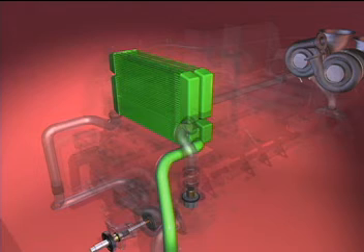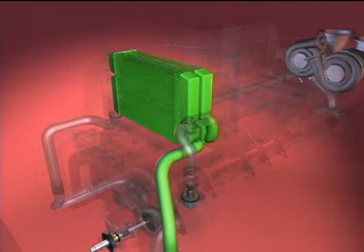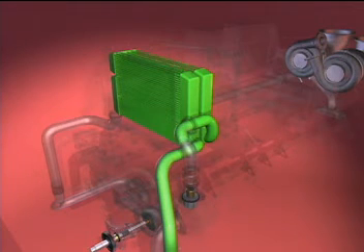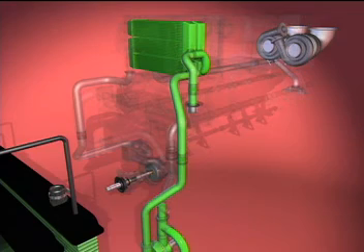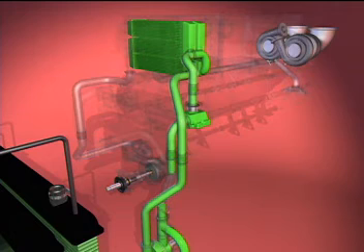A coolant return pipe connected to the bottom left side of the aftercooler directs the flow of coolant to the LTA section of the thermostat housing. In this part of the housing, the LTA coolant flow circulates around the temperature sensing bulb of the LTA thermostat. When the coolant at the thermostat is below the thermostat modulating range, the thermostat is closed, allowing the coolant to flow through the center of the thermostat. The coolant then flows to the front of the housing and back out the bypass connection to the inlet of the LTA water pump.